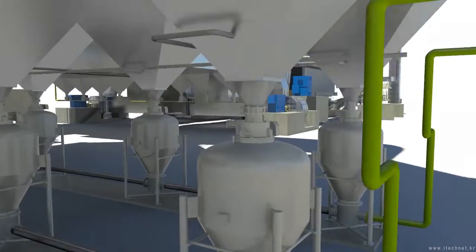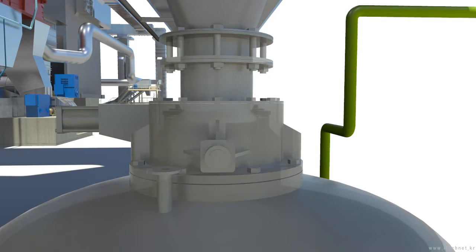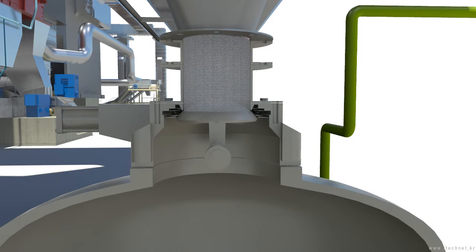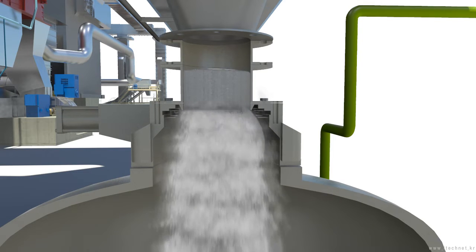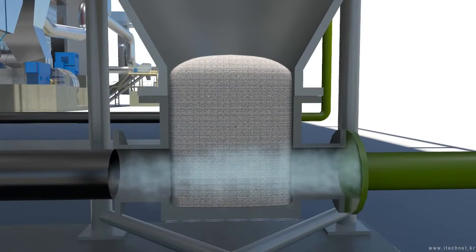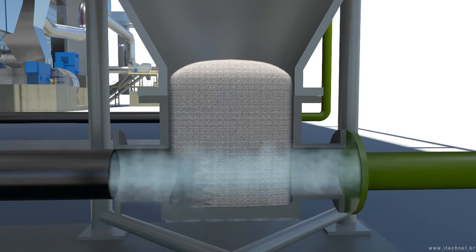The ash which is collected at the hopper of each system drops into the inside of pump after opening the valve. When a certain amount of ash fills up the pump, the valve is closed and sealed so that the ash won't fall into the pump. The ash which is collected in the pump is transferred through the pipe by compressed air of the compressor.